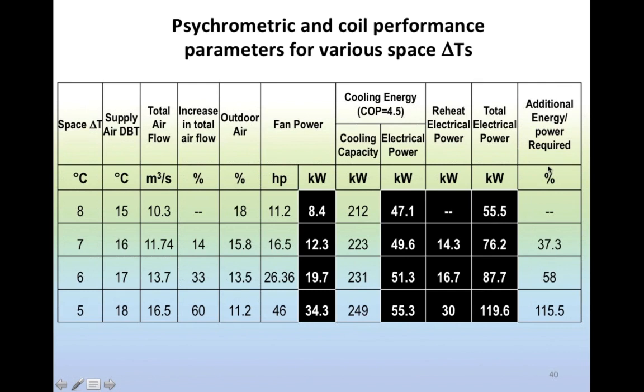I have a certain level of energy consumption, and of course that's my base case, so there's no difference, no additional energy required. If I change that to a 7 degree delta T, it's going to get worse because, as I said, the smaller the delta T means my off-coil condition, and thereby the space supply air condition, is getting warmer. The warmer it is, the more energy it's going to be consuming. The reason for that is there is extra cooling to be done, the overcooling part, to address the humidity issue, and then the additional reheat consumption that we need to provide for.